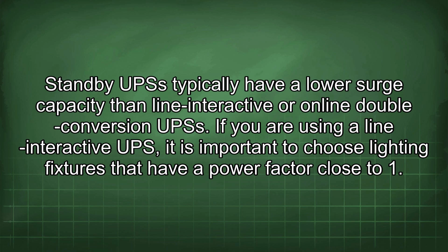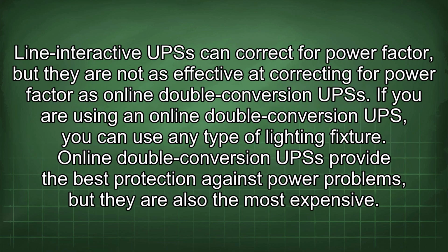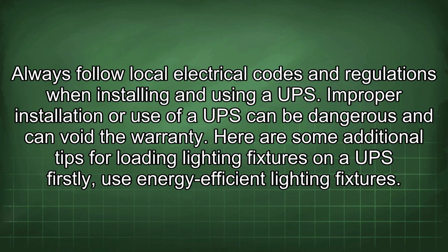If you are using a line interactive UPS, it is important to choose lighting fixtures that have a power factor close to 1. Line interactive UPS can correct for power factor, but they are not as effective at correcting for power factor as online double conversion UPS. If you are using an online double conversion UPS, you can use any type of lighting fixture. Online double conversion UPS provide the best protection against power problems, but they are also the most expensive. Always follow local electrical codes and regulations when installing and using a UPS. Improper installation or use of a UPS can be dangerous and can void the warranty.